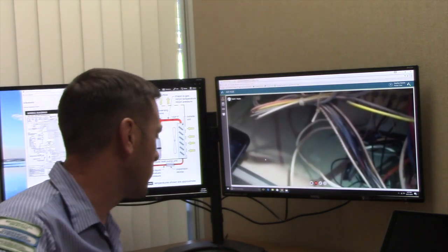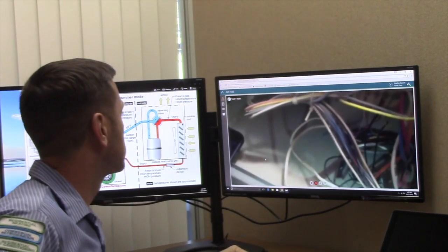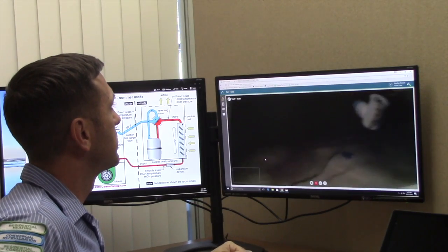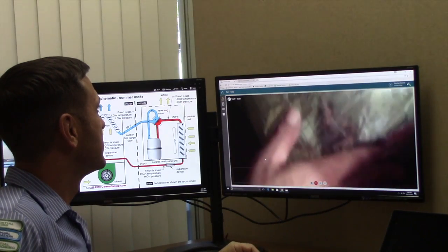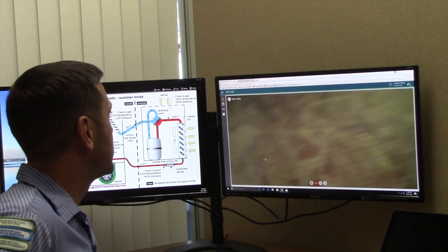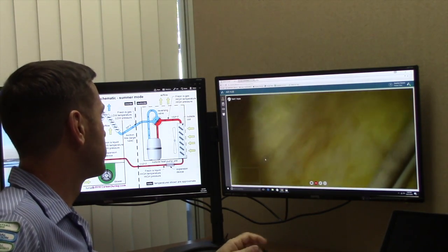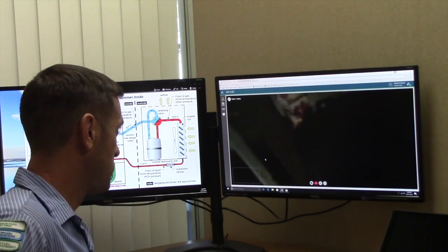Did you check the ductwork for leaks or kinks? I looked around a little bit. Looks like it's got mastic on this. Nice, good. How's that insulation level look in that attic? It's actually pretty clean, plus he has insulation up on the... Very good. You see the drain pans? Okay. Doesn't look like it's been used.